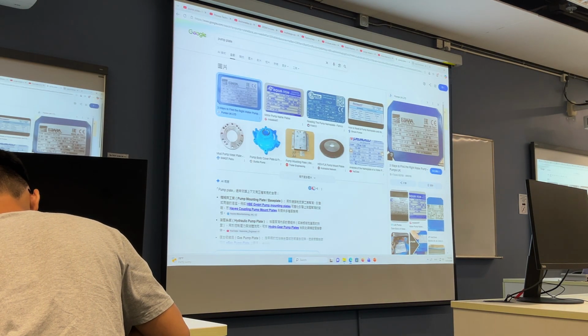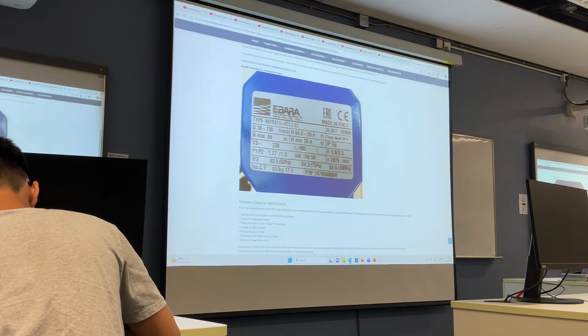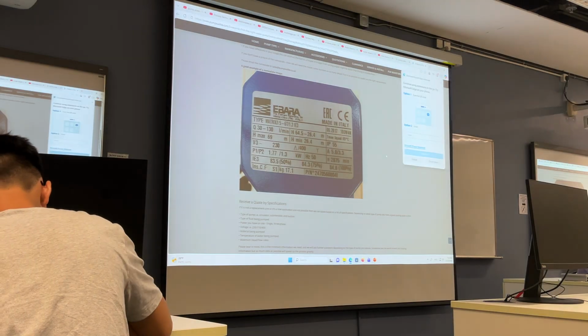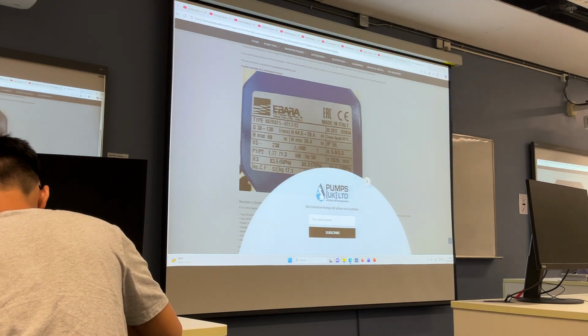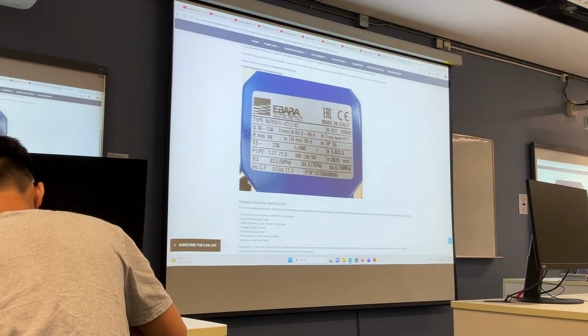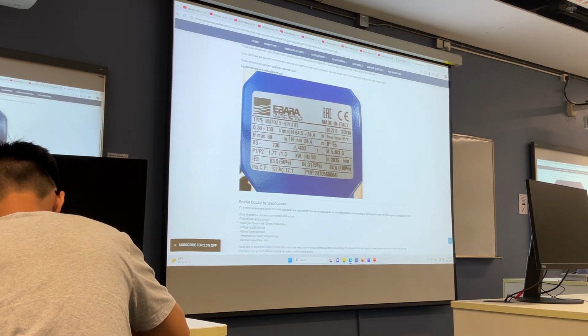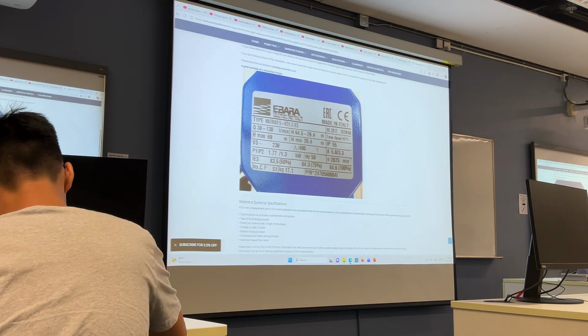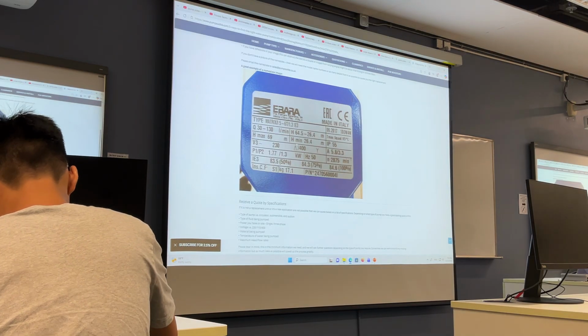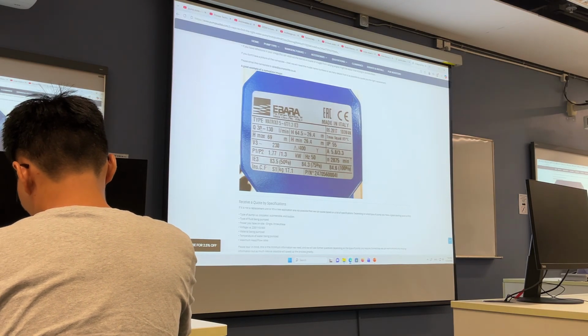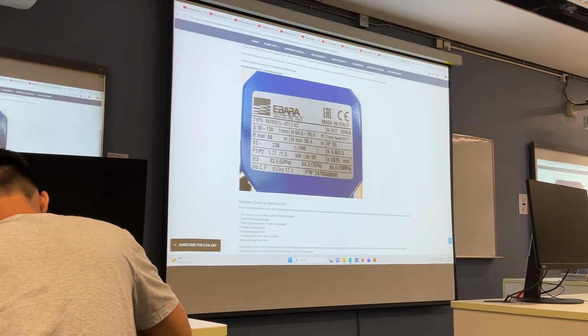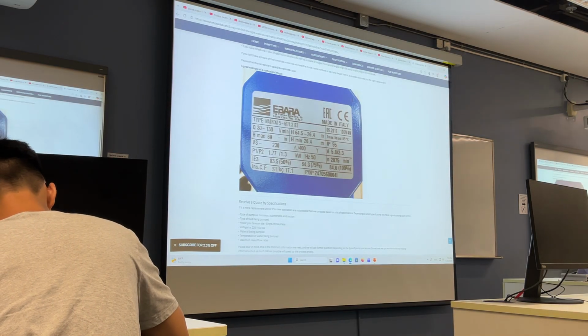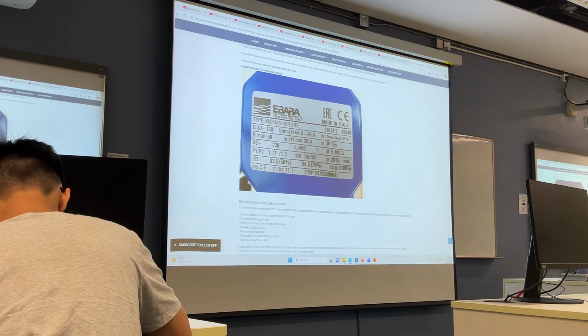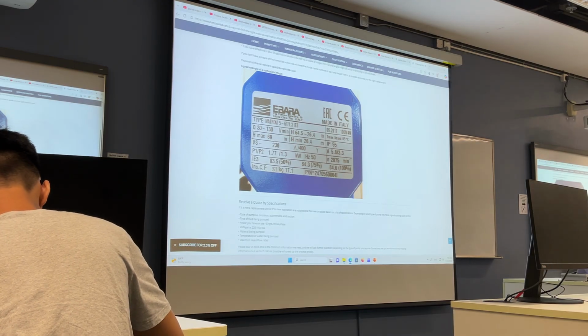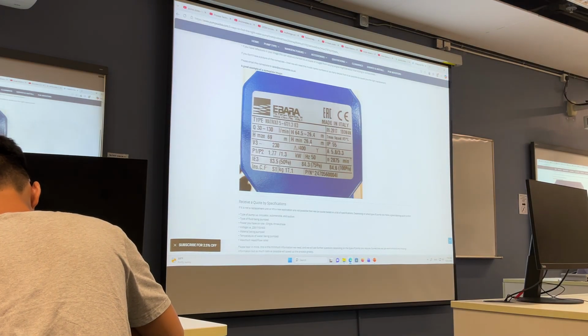Now, I randomly searched for a pump plate, just like this. This is a type of pump plate that is attached to the pump surface, so you will find information about the maximum discharge and the maximum pump head. For example, this one, but usually most of the pumps indicate this. I think this is a small pump: small discharge, but high pump head. It can be maximum and minimum.